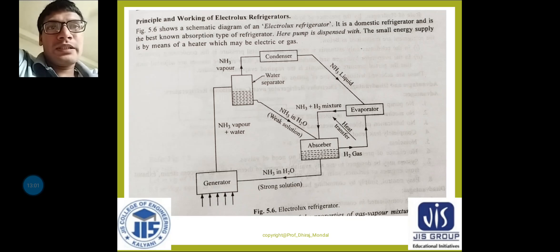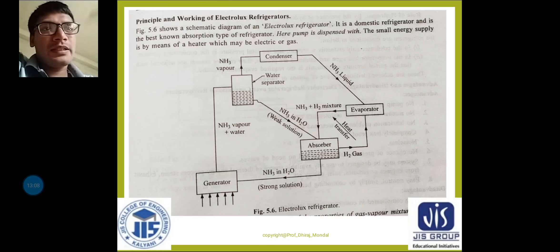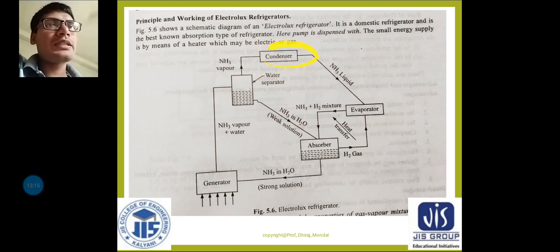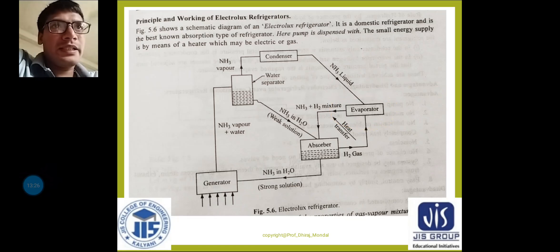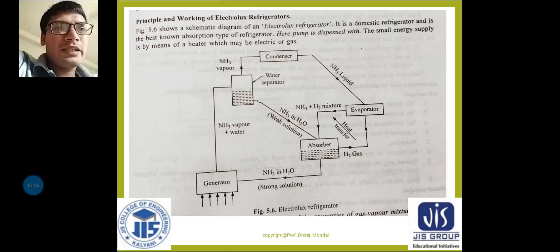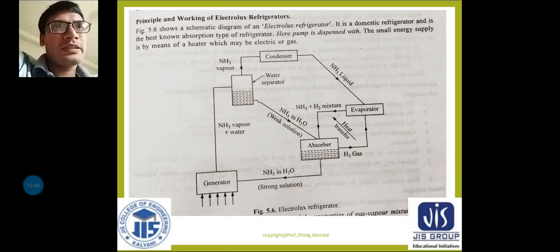The partial pressure of ammonia is kept low in the required parts of the circuit by concentrating hydrogen in those parts. The ammonia liquid leaving the condenser enters the evaporator, where it evaporates into the hydrogen — in the evaporator, hydrogen gas circulates between the absorber and evaporator, and ammonia and hydrogen mix together.